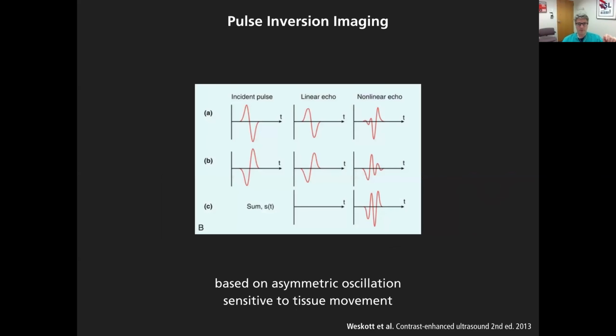The more modern ones depend on the microbubble having a non-linear echo response. If you look at the first column, what the ultrasound machine does is send out an incident pulse, and immediately afterwards send out an inverse pulse. And if you have a linear echo, that's the middle column, like normal tissue, they will cancel each other out because they respond linearly.